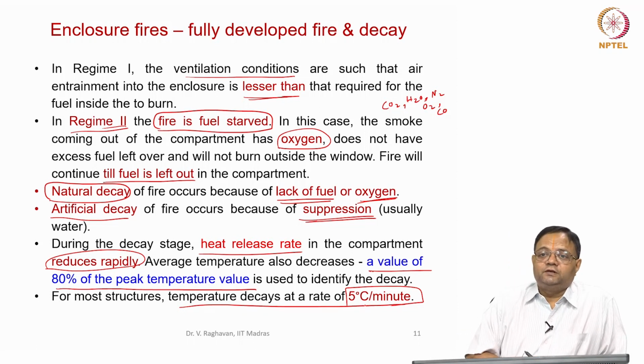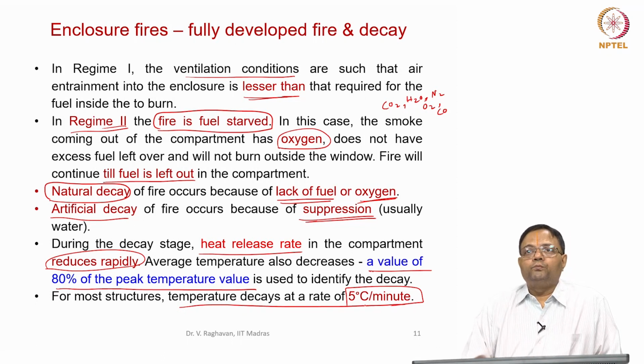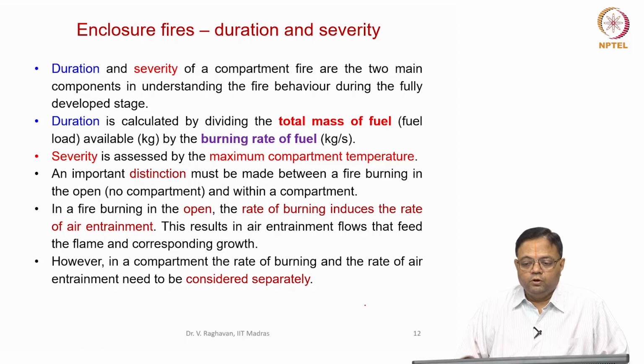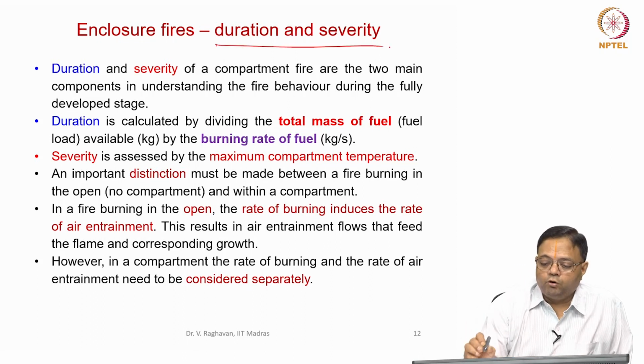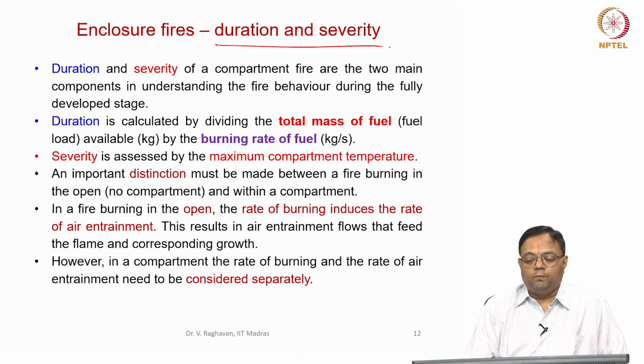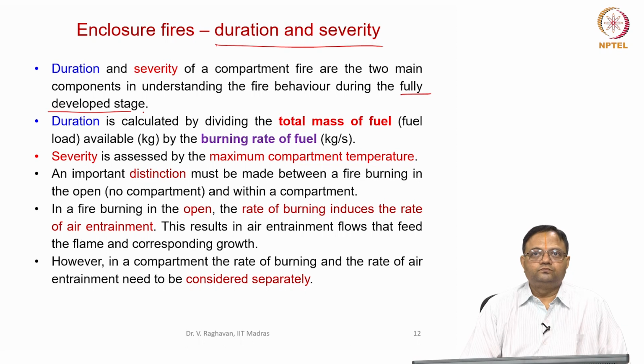And in the fully developed stage, we have two important aspects. One is, in some cases due to poor ventilation, the fire will be oxygen starved, and in some cases where a lot of oxygen can entrain into the compartment, the fire will be fuel starved. Now, we will talk about the duration and severity of compartment fires. These are the two main components to understand the fire behavior, especially when the fully developed fire has occurred.